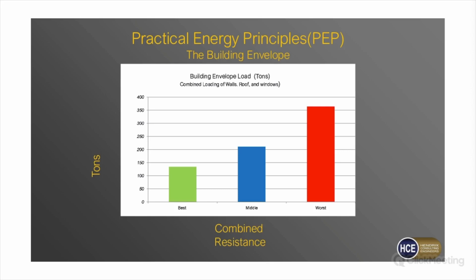The other thing we look at is combining the loads from all three: walls, roof, and windows, to see the total load for the whole building envelope. The glass can make a big difference in how this performs. Your roof and walls don't care about orientation, but your glass does. If we make good choices on materials and pay for the extra R value, we could be around 130 to 140 tons of envelope load for this square footage.